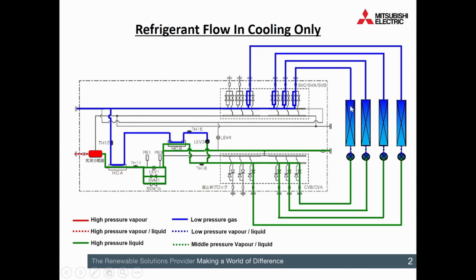And the way that we control the compressor back at the outdoor unit is it looks at that 0 degrees evaporating temperature, or 7.2 bar, and as I close down that expansion device, therefore you're dropping the pressure on this side. To bring that pressure back up, I slow down the speed of the compressor. As I open out the expansion device to do more work, the pressure changes on the other side of the indoor units, therefore I have to speed up the compressor to bring it back down to 7.2 bar. So that makes sense. So there's that refrigerant passing back.